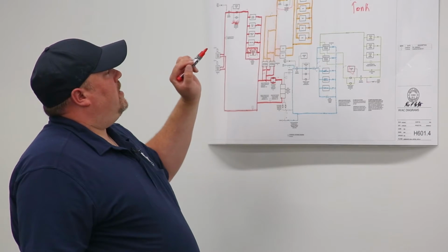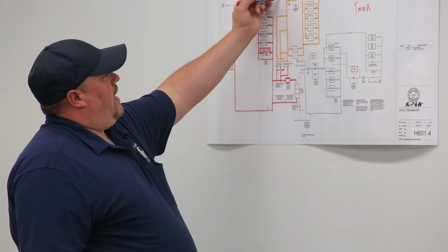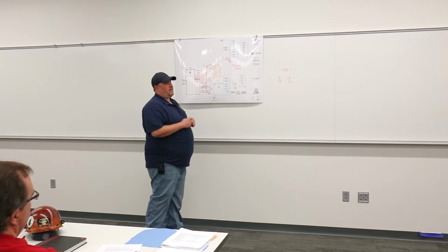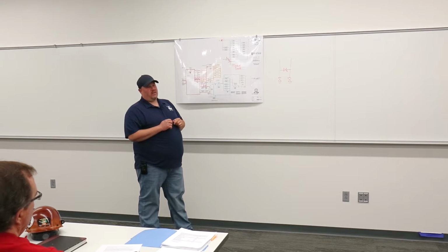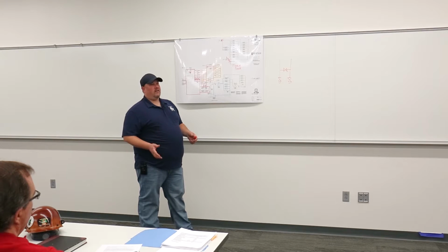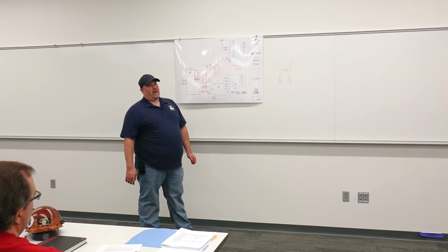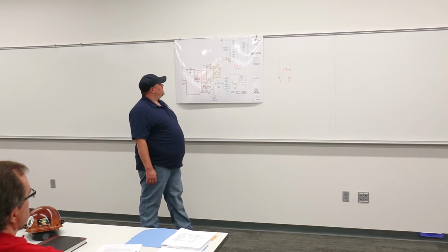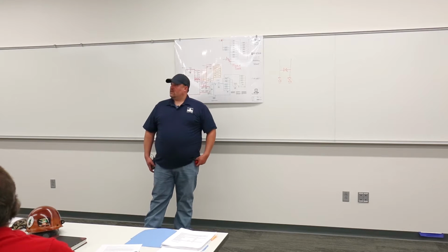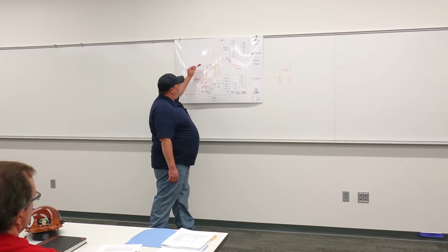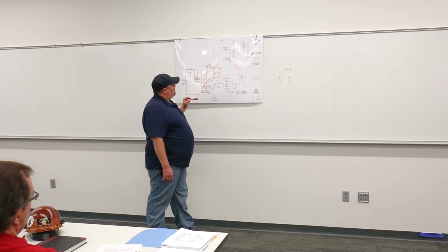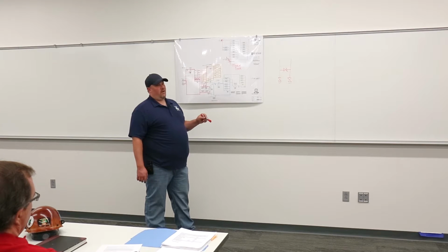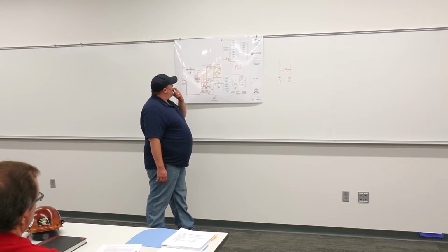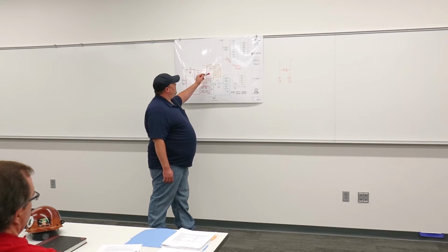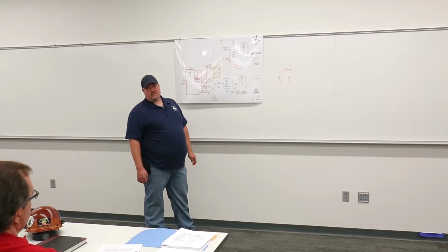Our glycol loop, on the other hand, in the penthouse for the Convecta pack, has a glycol fill tank. There's an actual automatic glycol fill feeder located in the penthouse that is set for, I do believe, 30 PSI, that will automatically kick on and fill. It has a containment of 55 gallons and will go into alarm when water levels or glycol levels get low. Okay. Should we mention it's a 30% premixed glycol? Yeah, maybe. The glycol makeup water feed and the glycol contained in this loop is a premix of 30% glycol. Propylene? 30% propylene glycol.